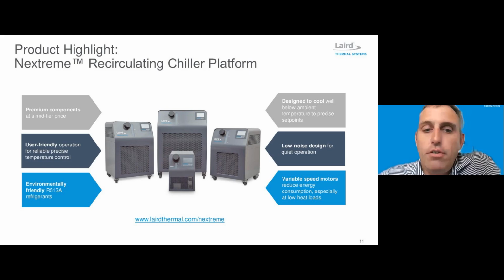The refrigerant that's used here also, we've gone over this a little bit, but the one that we use in this product is called R513A. This is kind of a half step between what's commonly used in the industry today and getting to those alternative near zero GWP refrigerants that are becoming more of the norm. So this refrigerant has anywhere from about half to 1/8 of the GWP that's commonly used in the industry today. So it's about half of R134A, and then if we look at some of the other ones like R404A, it's about 1/8 of that.